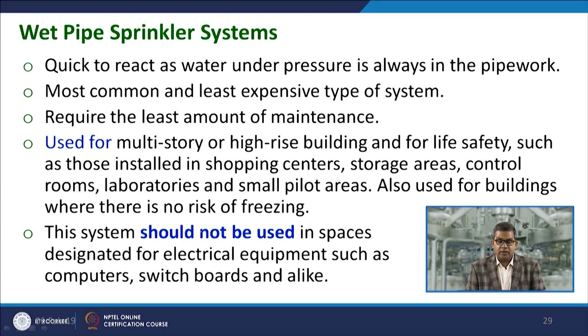Used for multi-storied or high-rise buildings and for life safety, such as those installed in shopping centers, storage areas, control rooms, laboratories, and small pilot areas. Also used for buildings where there is no risk of freezing. Now, this system should not be used in spaces designated for electrical equipment such as computers, switchboards, etc. The reason is that the chances of streaming electricity may be high in case of a fire.